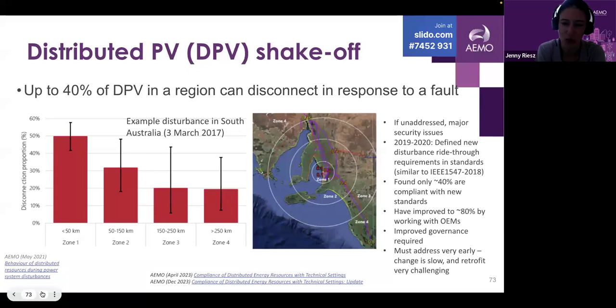the minimum voltage is recorded about 0.1, 0.2 per unit. In response to that, we saw a very large proportion of the distributed PV trip off. Within a 50-kilometre radius, it was about half of the PV that tripped, and extending right out to about 250 kilometres away, which covers a lot of the state.